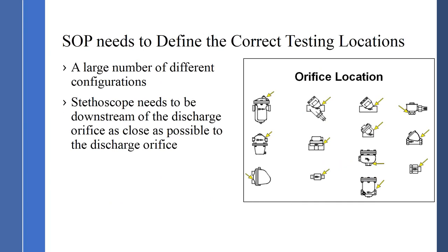The SOP goes through the different configurations of steam traps and where to place the stethoscope module when testing. You want to be downstream of the discharge orifice — that's where the highest degree of ultrasound is generated and where you want to be testing. The team should carry sample diagrams with them so when they walk up to a steam trap they can identify it as inverted bucket mechanical, float thermostatic, thermodynamic, bimetallic thermostatic, or bellows thermostatic, and know where to put the stethoscope module.